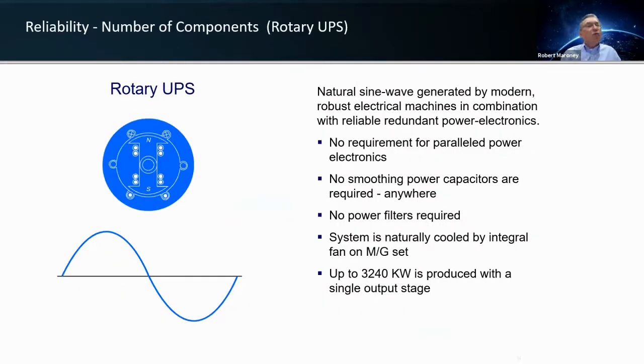So let's talk about how a rotary machine works a little bit. By using a rotary machine or a motor generator, a spinning mass, we generate a natural sine wave through using that very large, robust motor generator system. We don't have to parallel multiple power electronic or multiple power stages like a multi-module system to get to powers above 500 kilowatts. No smoothing capacitors in the system, no filters in the system.